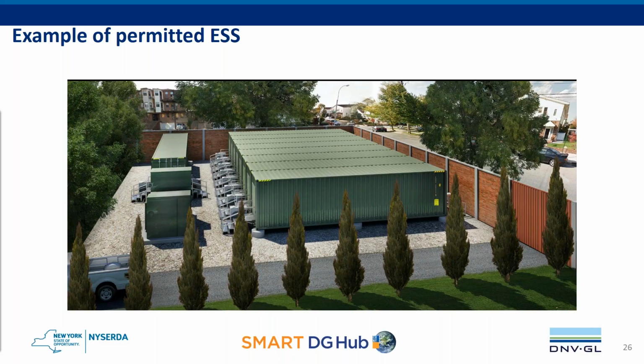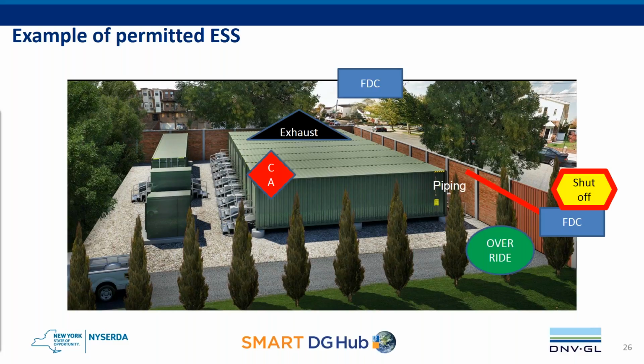So this is kind of a busy slide here, but the New York City Fire Department really looked at this and they wanted to make sure that they could keep the responders safe in the event that there was an incident. They really wanted to make this a non-intervention. As you can see, that CA here on the bottom stands for clean agent. When these things were originally designed, they had a clean agent already installed inside of them. The New York City Fire Department felt that they needed something beyond the clean agent, and they wanted to put water inside there.